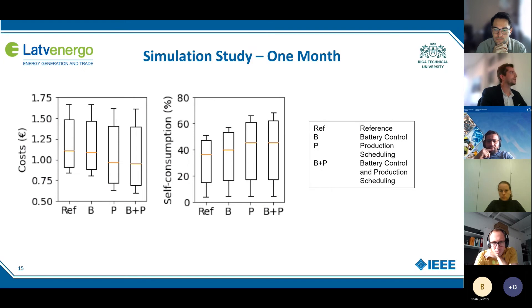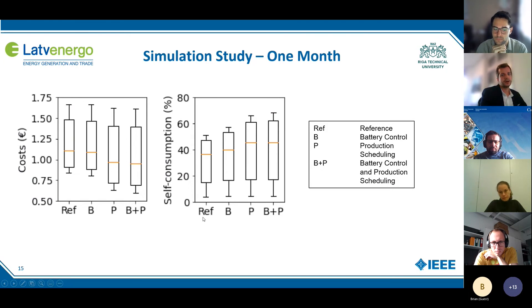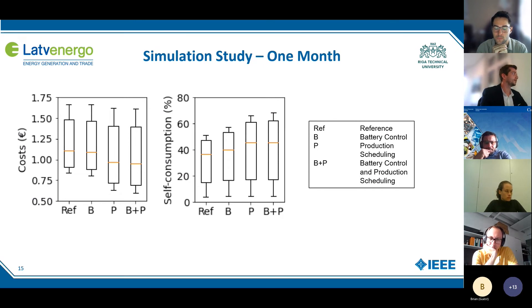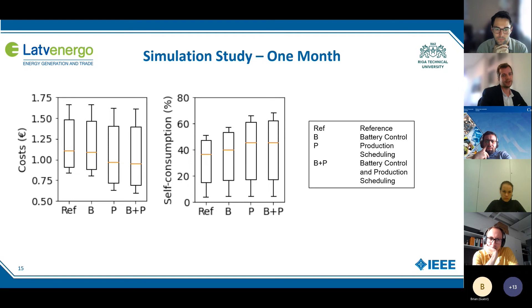Let's talk about the results. Here we can see the results of the simulation study for one month using spot market prices. On the left we can always see the reference case, where the production starts as soon as the production order list arrives. There we can see a clear mismatch between production and energy supply, resulting in low self-consumption. The next case is optimal battery control. We can see that with optimal battery control, the costs aren't really better than the reference case. This is due to the high investment and degradation costs of the battery, and also these are calculated with electricity prices from last year, so this year it would look different.